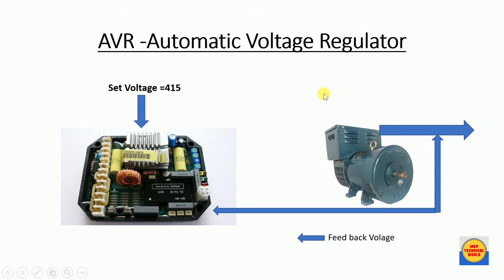Next is the AVR — Automatic Voltage Regulator. The AVR maintains constant output voltage and also controls the DC excitation of the alternator. We can set a reference voltage, and the AVR takes feedback voltage from the output terminal of the alternator. The controller compares output voltage with reference voltage, and according to the error signal — the difference between reference and feedback voltage — it controls the DC excitation of the field winding to maintain constant output voltage.